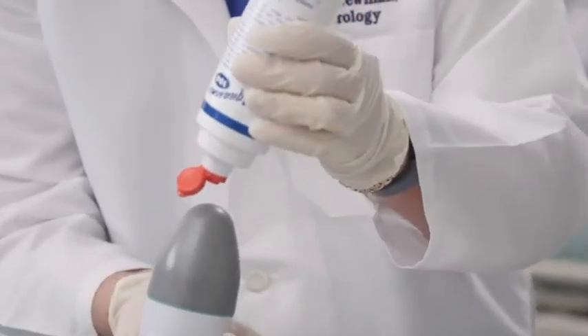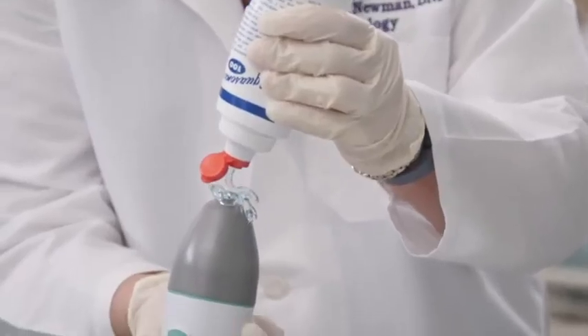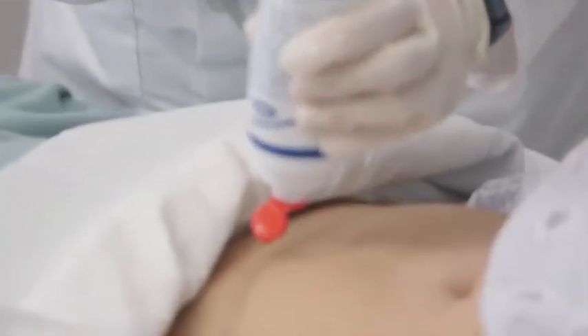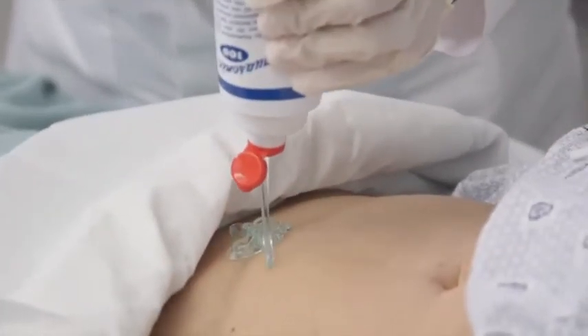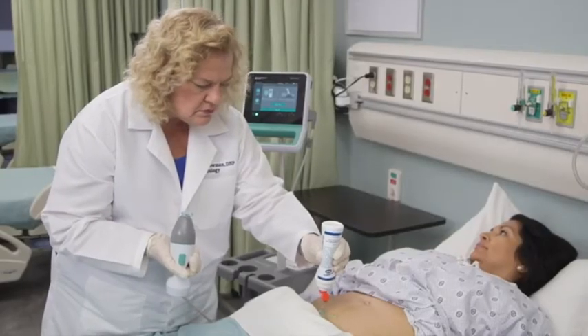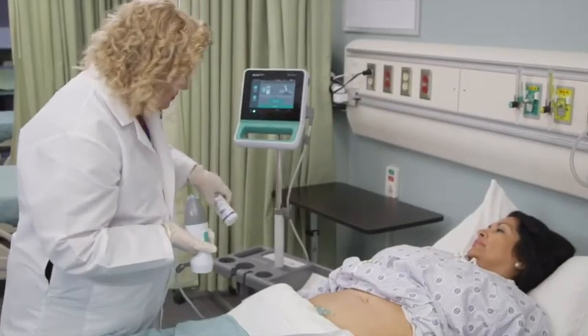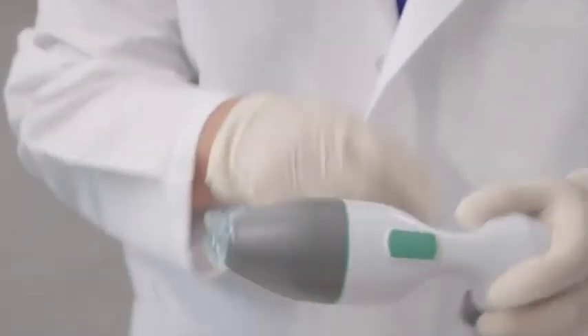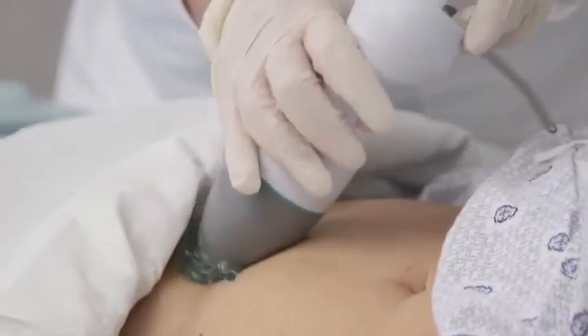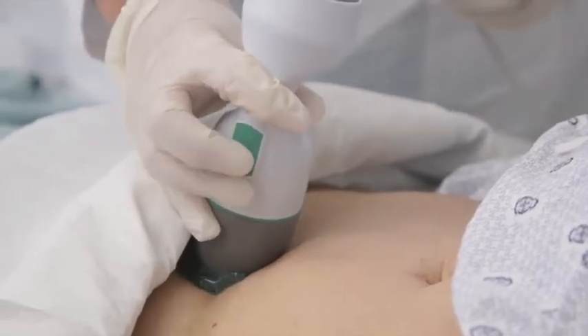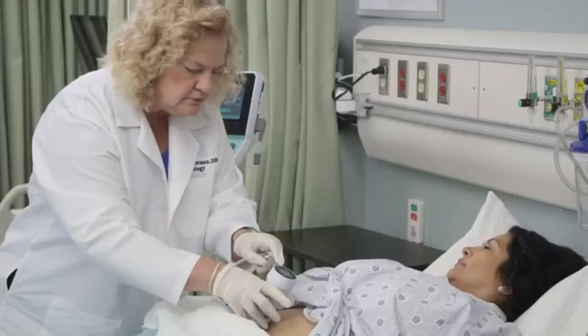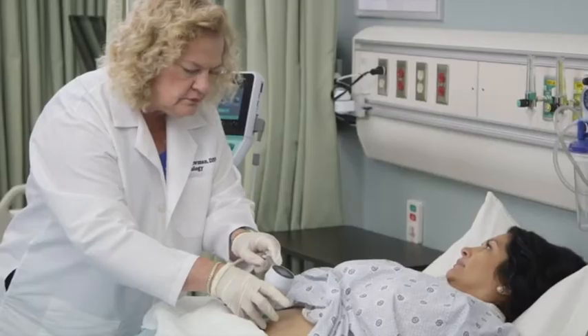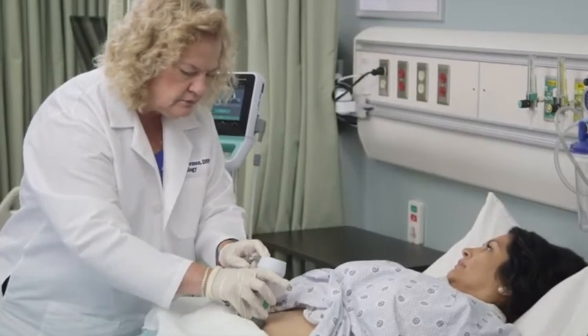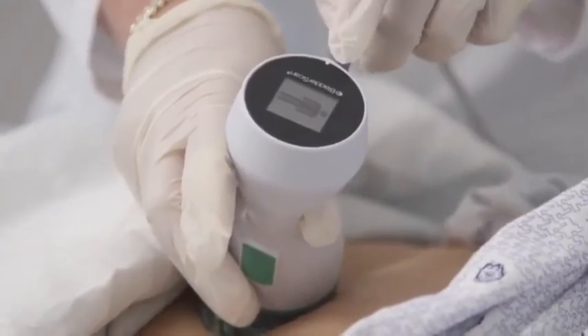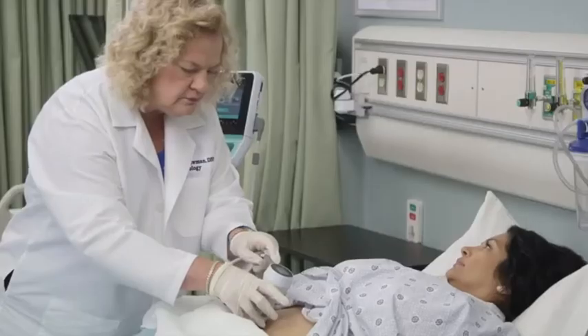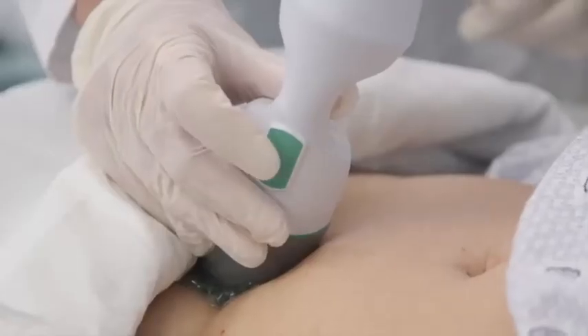Apply a generous amount of ultrasound gel to the probe or directly on the patient's skin. Be careful not to touch the gel bottle tip to the probe or the patient's skin, as this risks cross-contamination. For best results, keep the gel in a thick layer. Don't spread the gel too thin, as this may result in poor contact between the ultrasound probe and the patient's skin. Using the icon on the probe display, be sure to align the probe with the long axis of the body. To begin live pre-scan aiming, press and release the scan button.